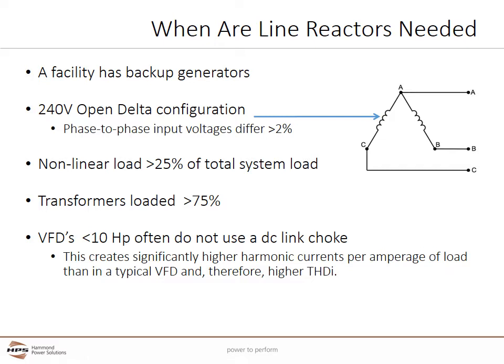If the transformers are loaded more than 75% of the rated nameplate, line reactors should be considered. VFDs less than 10 horsepower often do not use a DC link choke. This creates significantly higher current harmonics per amperage or load than in a typical VFD, and therefore higher total harmonic current distortion can occur, and line reactors should be considered.